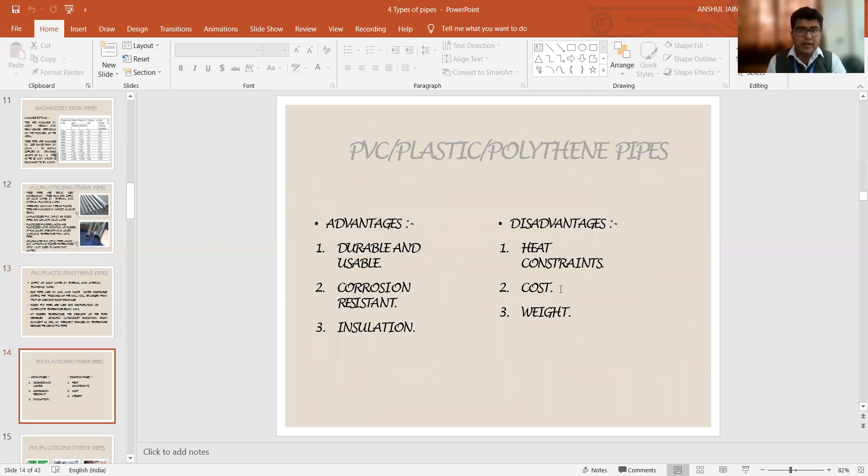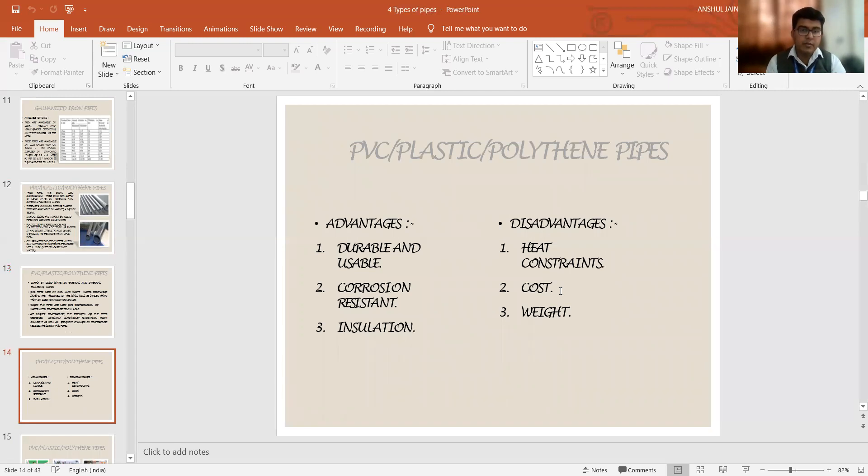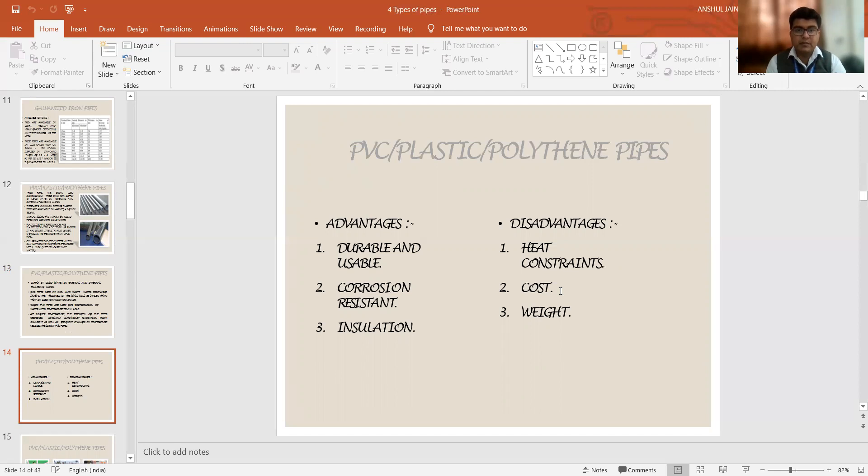The advantages of these plastic pipes is their durability and usability in the desired forms you can convert it. You can mold it into the required formats. It is having good corrosion resistance because plastic is not easily affected by the weathering or the temperature conditions. Also, the insulation is an important property. If you are supplying hot water it won't allow the heat to actually pass through it, whereas in the case of the steel or the metallic pipe this is a big problem. They will get heated if you are supplying any 100 plus degree water from one end to the other end.